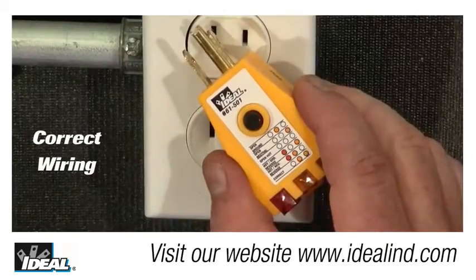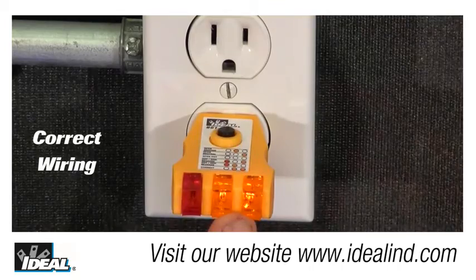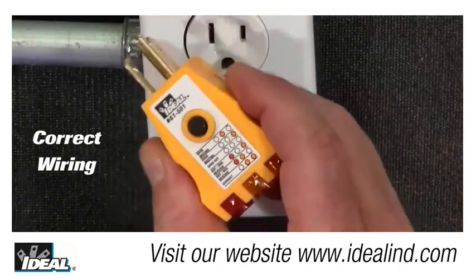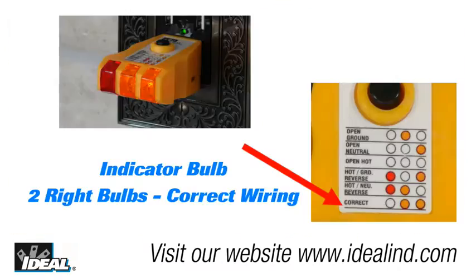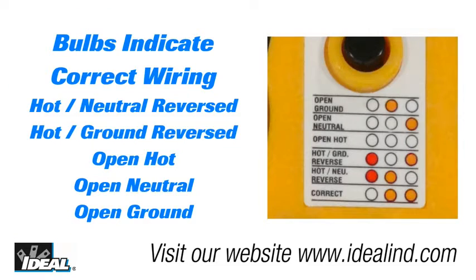Now, here I have a receptacle tester plugged into an electrical outlet that's actually wired properly. And as you can see, of the 3 bulbs on the tester, the 2 on the right are lit up. Now, looking at the legend on the tester, this indicates correct wiring. Next to each condition on the legend, it'll explain what the different bulb combinations mean, and a white dot represents a bulb that's not lit up.